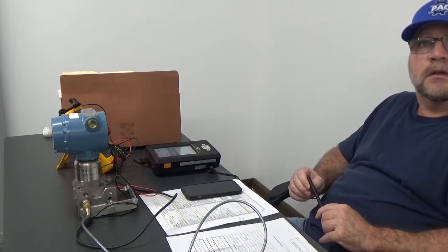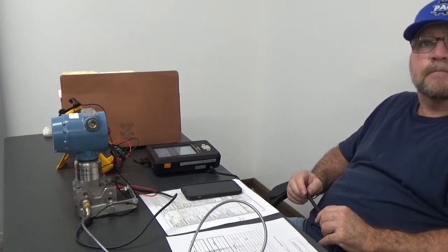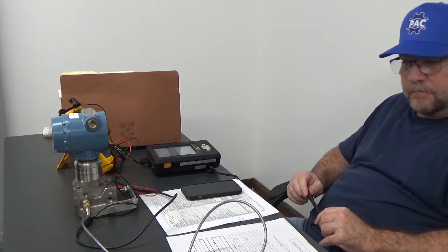I want you to go to whatever your 25% pressure is, whatever the number is, write it down. I don't care what it is. You go to your 50% range and tell me whatever the milliamp is, and do the same thing at 75% and 100%. Then you will calibrate it. And once you calibrate it and you're satisfied with the calibration, you will write those numbers as left.